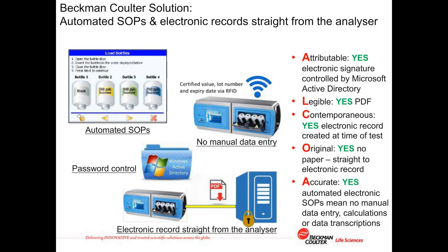All right, okay. So if I understand correctly, you've taken the PDF file and you've printed it out into paper format. So your raw data, your final record, is a paper printout which you're manually signing. So effectively that's the same as any paper record. And if you read the 2003 guidance from the FDA, it actually says that if that is the final record and that's the record you go to when the FDA call upon you to produce the evidence for batch quality, and you never go back to the electronic record at all, then in theory 21 CFR Part 11 doesn't apply at all. That's what the FDA say in their guidance. If it's a paper record you use, the computer or the system that you use to generate that paper record doesn't need to comply with 21 CFR Part 11 as long as you never go back and rely on the electronic records again.